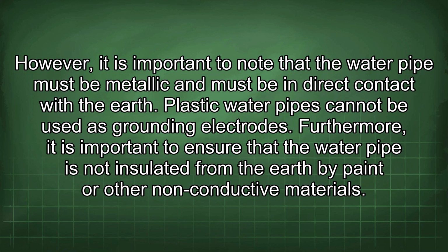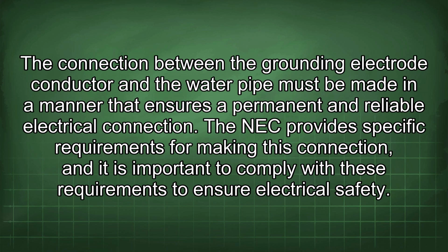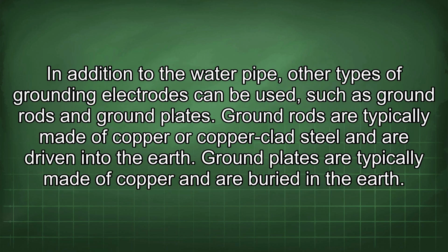Furthermore, it is important to ensure that the water pipe is not insulated from the earth by paint or other non-conductive materials. The connection between the grounding electrode conductor and the water pipe must be made in a manner that ensures a permanent and reliable electrical connection. The NEC provides specific requirements for making this connection, and it is important to comply with these requirements to ensure electrical safety.